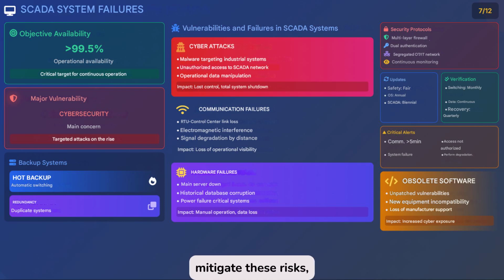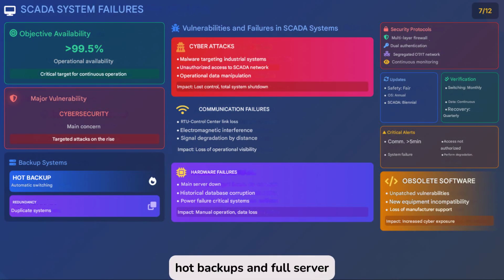To mitigate these risks, robust measures are required: multi-layer firewalls, dual authentication, segregated OT/IT networks, and continuous monitoring. Furthermore, periodic testing, such as monthly switchover, data verification, and recovery drills, are key to ensuring resilience. Backup systems, such as hot backups and full server redundancy, allow operations to continue even during failures or maintenance tasks, reducing technical downtime and improving overall availability.